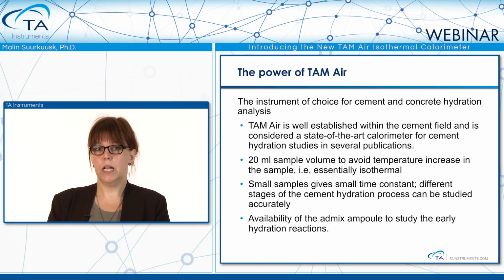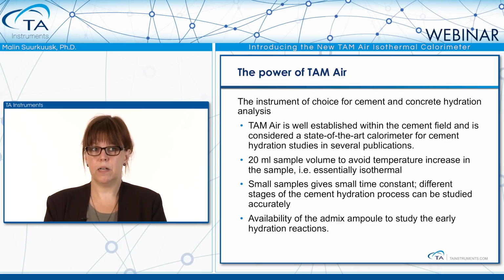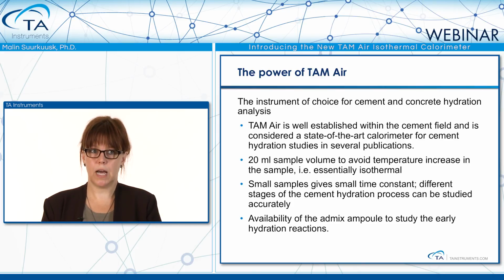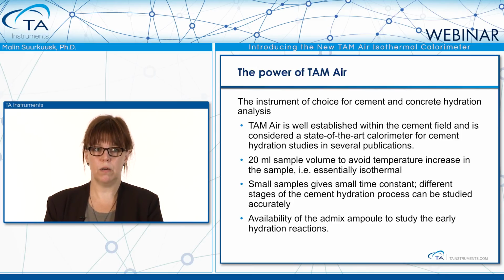And if we specifically look at using TAM Air in the cement and concrete analysis field, TAM Air is well-established within this field, and is considered a state-of-the-art calorimeter in several publications for just cement hydration studies. It has a 20 milliliter sample volume to avoid temperature increase in the sample, which means that this is an essentially isothermal measurement. And the small samples also give a small time constant, so the different stages in the cement hydration process can be studied accurately.